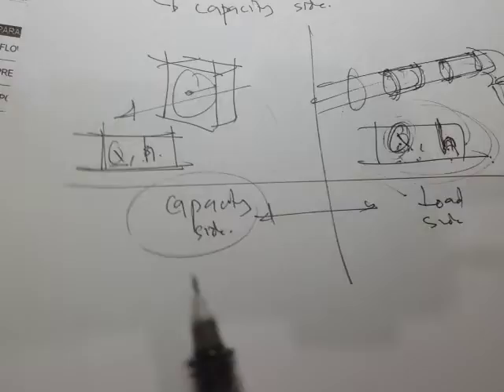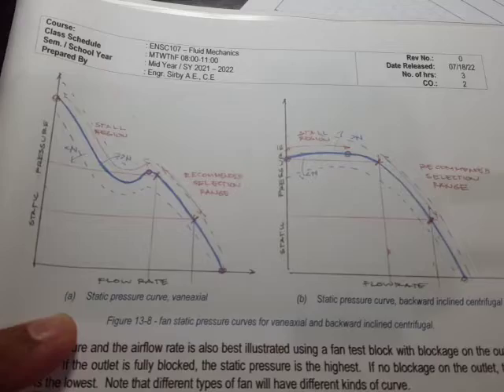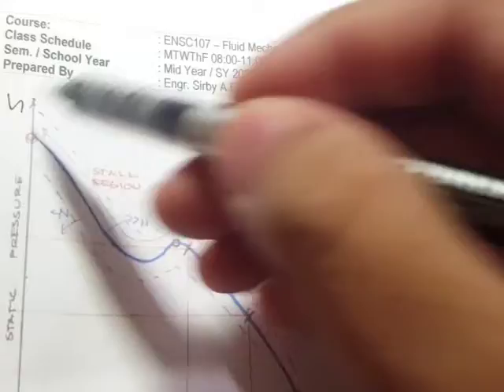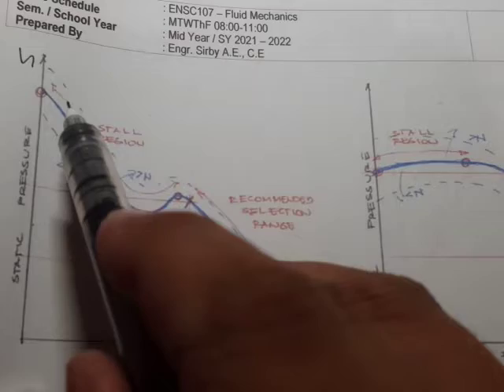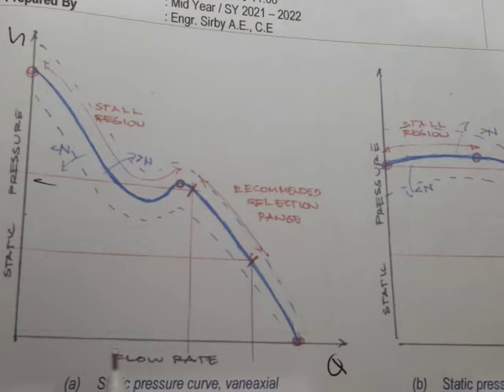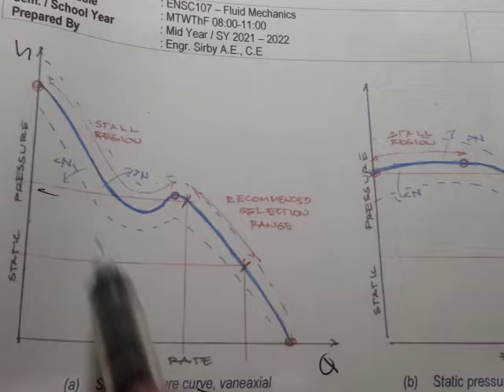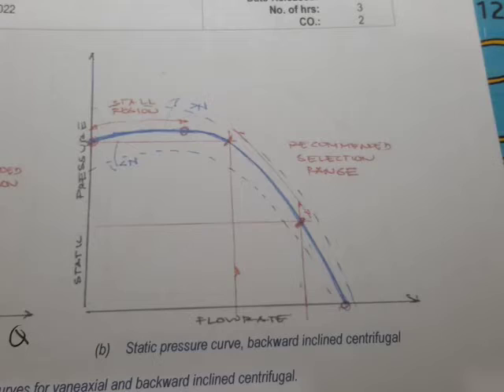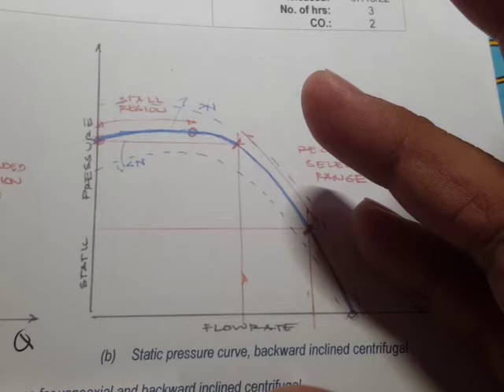A fan performance curve is basically a graphical representation of the performance of a specific fan. Different fans have different performance curves. For example, a static pressure curve for vane-axial fans looks different from a static pressure curve for backward-inclined centrifugal fans. The x-axis is flow rate Q and the y-axis is static pressure H.